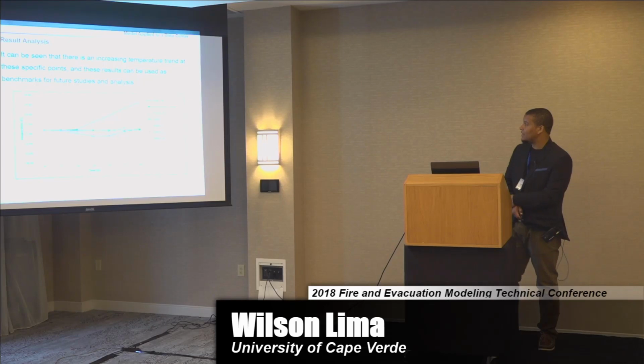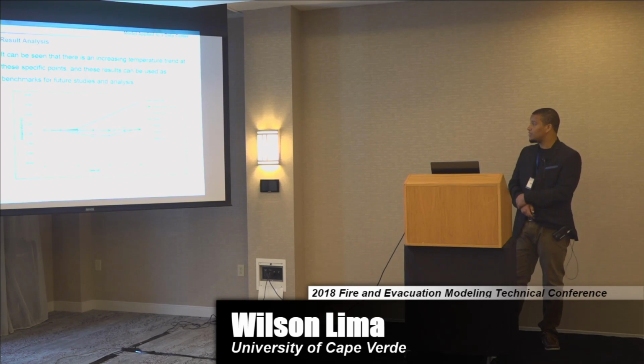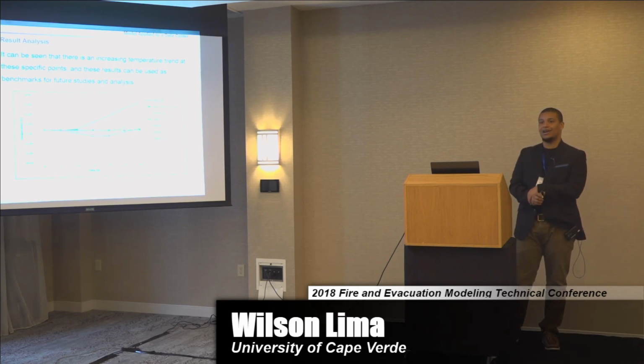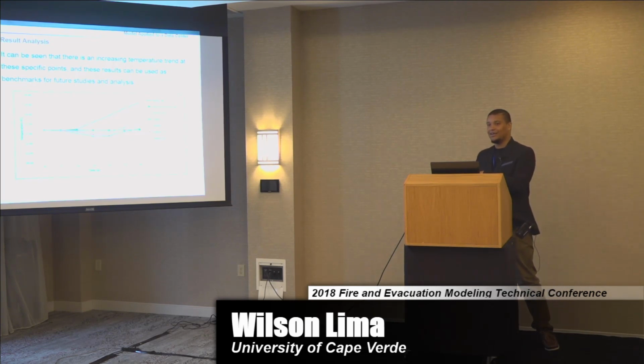So here we present the heat detector's results, where it ranges between about 21.15 Celsius degrees and 24 Celsius degrees. If we walk into the data center with a thermostat in the doors of all servers, we will get the same result that we get in this model.